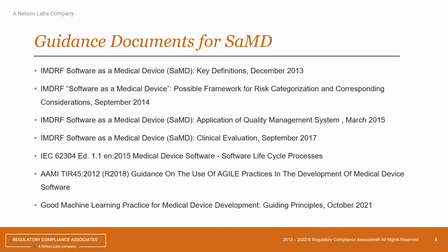Also, obviously, anytime you do software, IEC 62304 is the key guidance document that is used for that. And in case you're doing any sort of Agile development, it's all about the TIR 45 that allows you to do that for medical devices. And obviously, if you're doing any sort of AI/ML, then you better have your good machine learning practices in place. And there are definitely the guiding principles that FDA, Health Canada, and MHRA came out with.